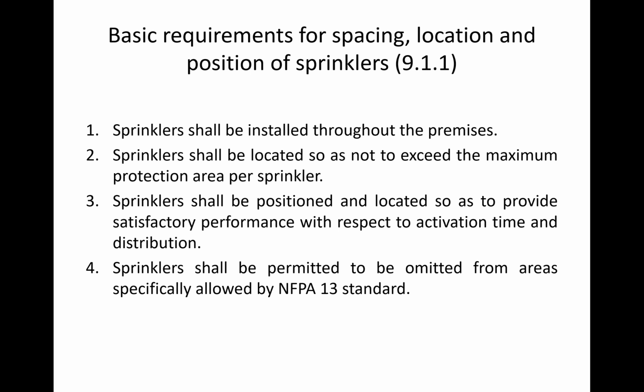Sprinklers must be located so as not to exceed the maximum protection area per sprinkler, and this is generally dependent on the hazard of the space. Sprinklers must be positioned and located so as to provide satisfactory performance with respect to activation time and distribution. And finally, and most importantly, sprinklers are permitted to be omitted from areas specifically allowed by this standard. And this is our main topic today.